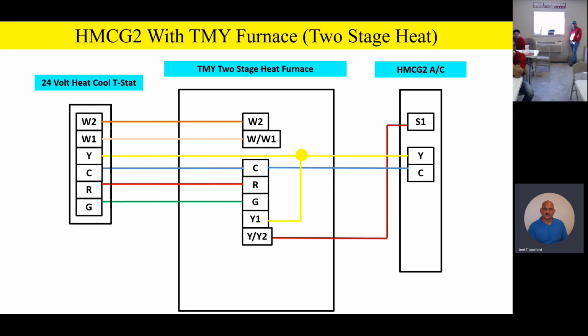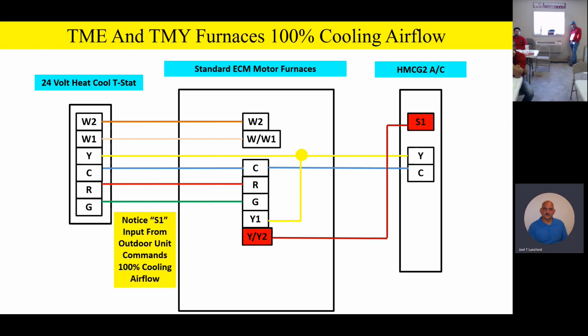So let me back up again one more time. The default airflow on the HMCG2, the straight cooling product, with the unit just sitting there and it calls for cooling, is 60% airflow. Then when the outdoor unit has been running a while and it says, hey, I need increased airflow because I'm at a higher capacity, it energizes S1 and drives the indoor unit to second stage airflow. So that's an important concept we have to remember, that on the straight cooling product, the outdoor unit S1 output directly commands our second stage airflow.